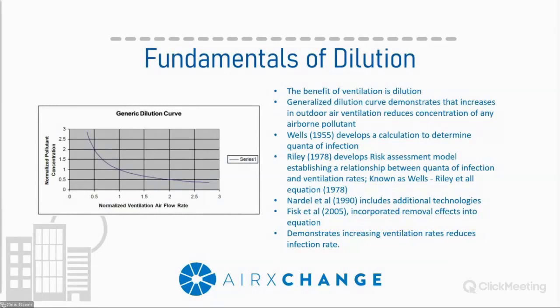The generalized dilution curve that you see on your left is often used to represent the reduction of contaminants based on a normalized airstream. And what it represents is that every time you double the air changes, you cut the indoor concentrations of contaminants in half. So this generalized curve is typically used to represent what most consider kind of normal occupied space air, and it doesn't really stem from any type of viral or health-related concern. But that's not saying there isn't a long history of studies that demonstrate that this curve has been used to form a relationship with risk reductions as you increase outside air.